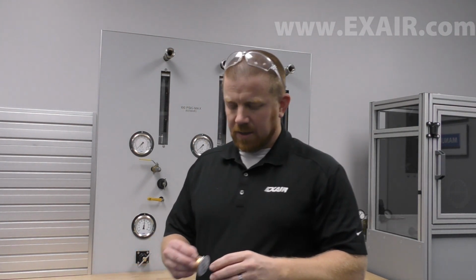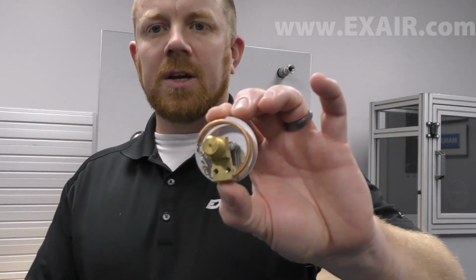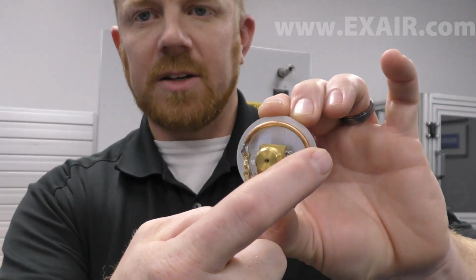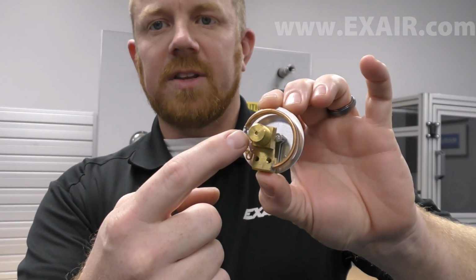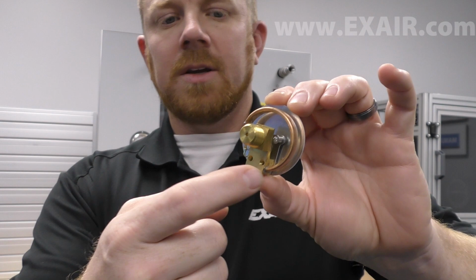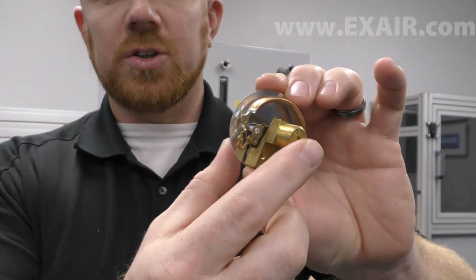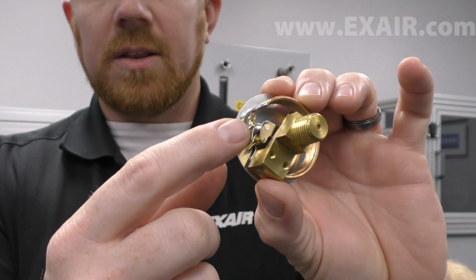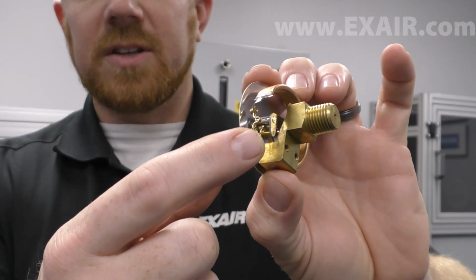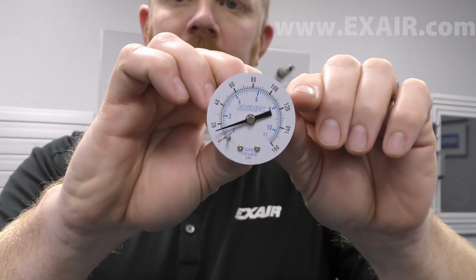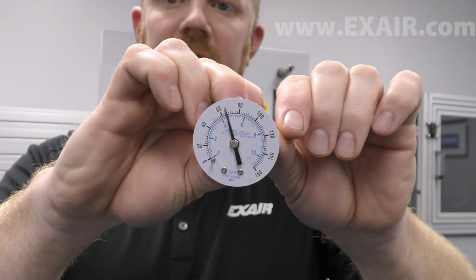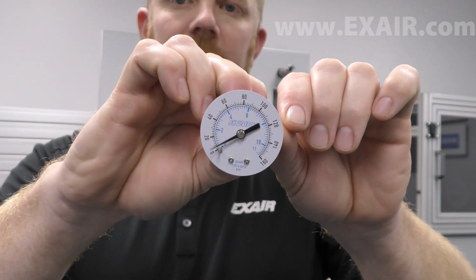The one I have here is the model 9011 and is just an everyday gauge. This analog style is also known as a Bourdon tube gauge, and it gets that name from this flattened curved tube. As the air comes into this orifice here, it will cause the tube to change shape, and that is connected to a rack and pinion inside of the gauge, which all connects out to the indicator on the gauge face. So as the tube increases, the pressure increases, the readout does as well.